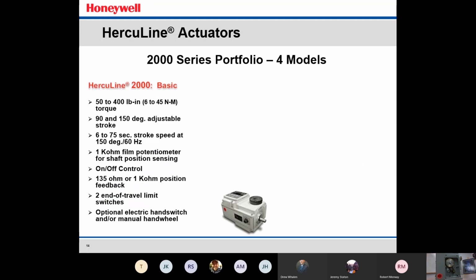Now let's talk a little bit about the Herculine 2000 series. There are 4 models available in the Herculine 2000 series. The basic 2000 series has up to 400 inch-pounds of torque, up to 150 degrees adjustable stroke. And based on the selection that you choose for your torque, it also has a 6 to 75 second stroke speed at 150 degrees. So as the torque increases on the actuator, the timing slows down. So at 400 inch-pounds at 150 degrees, you'll be at 75 seconds. There are other models where you can get into the standard 30, 60-second timing as well, but that's based on the torque that you select in the actuator.